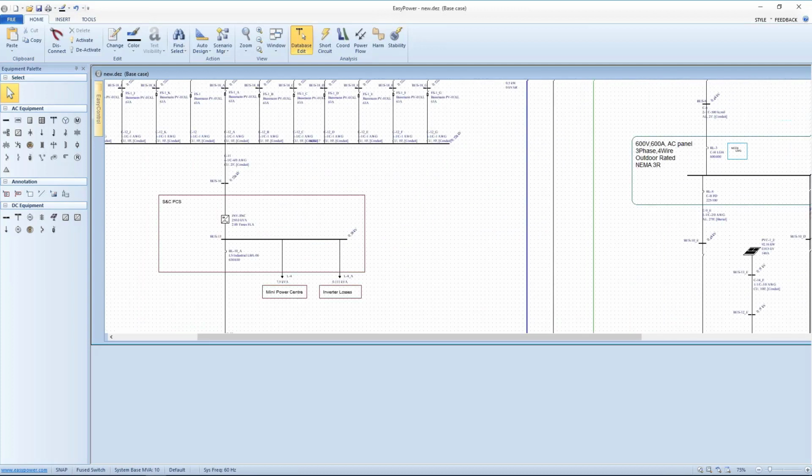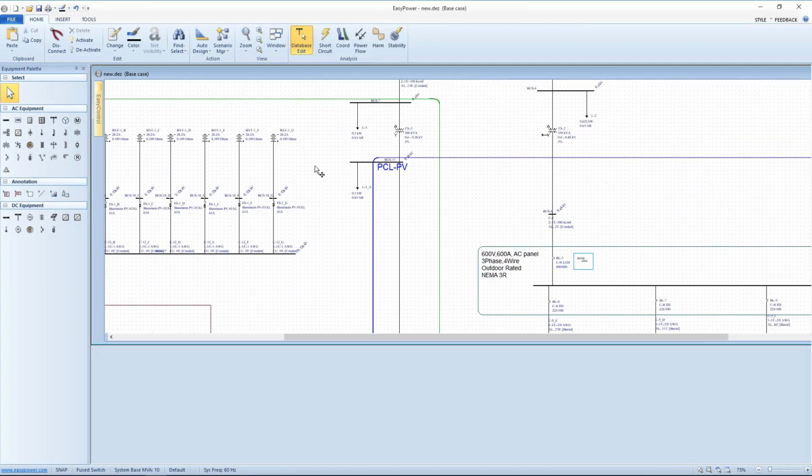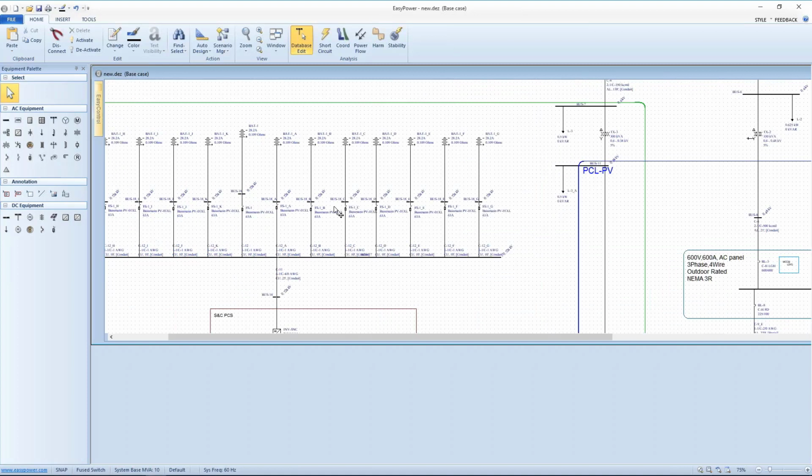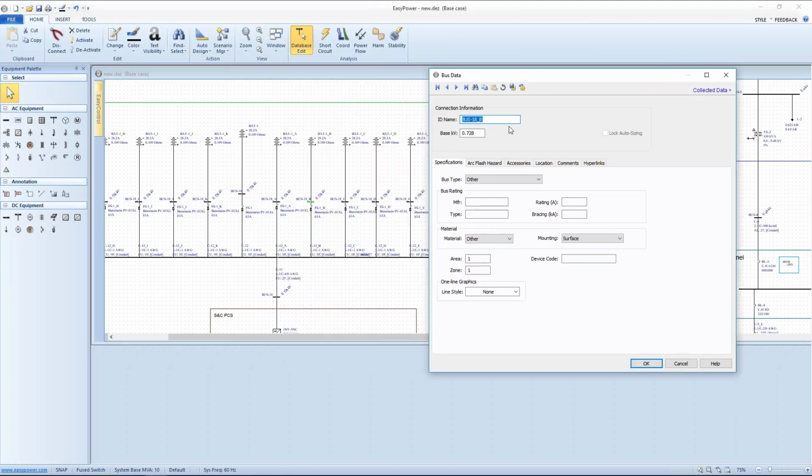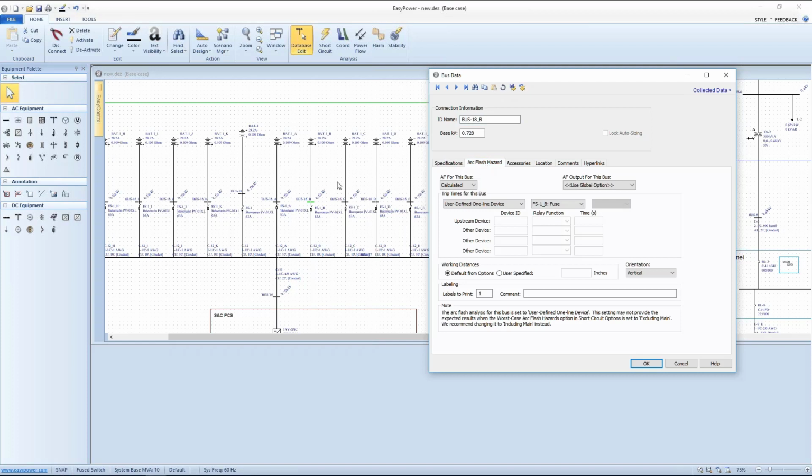The next point of concern is what's happening upstream of that. Oh, one more thing before I leave the batteries. When I come back and look at the way this bus is set up, and I'm looking at one of the upstream buses between the battery and the fuse, normally it would be looking downstream for the arcing protection, but downstream from the AC side means that the battery is the next element up there.